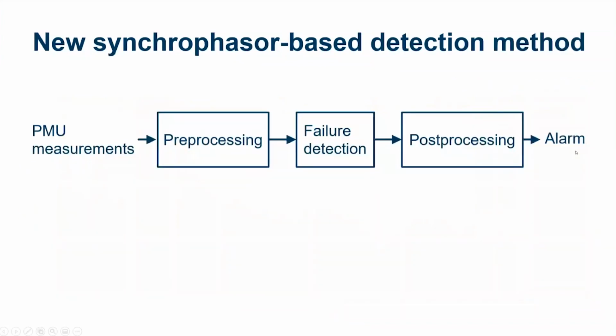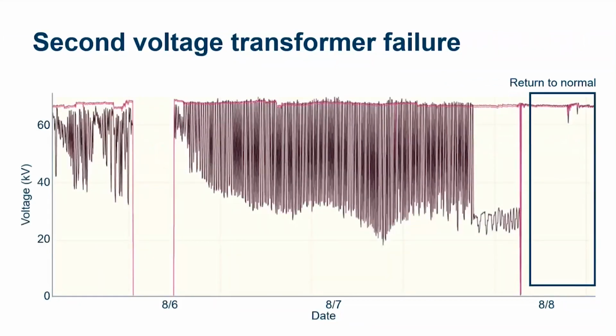So in both of these cases, in this last example, they had about a week's notice prior to the eventual failure. And in the example before that, they had at least 2 weeks, because they ended up replacing before an actual failure occurred that ended up compromising the system. But you can see in both these cases, by looking at the data over a period of time, we're able to make some decisions looking at that data that can help lead to improvements.